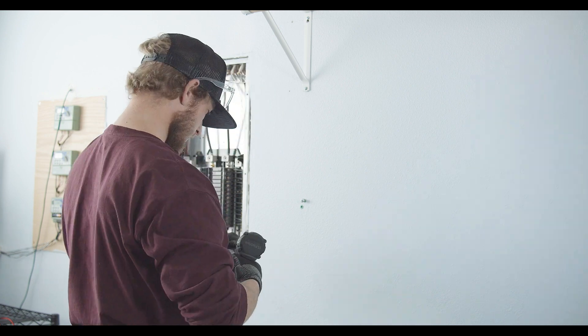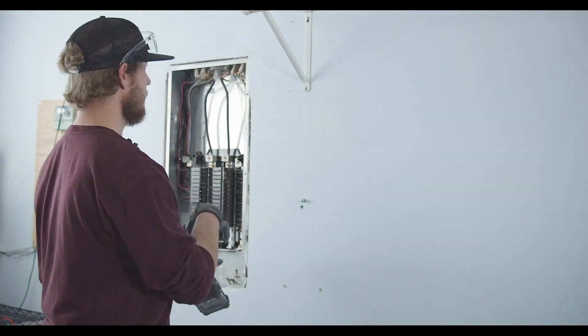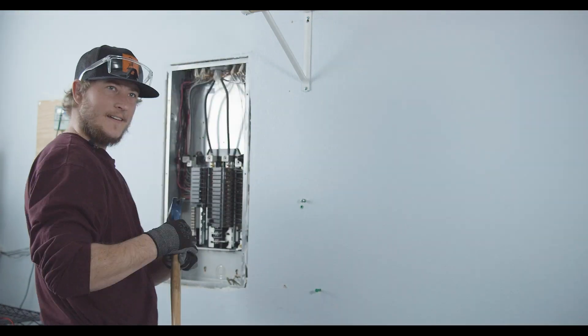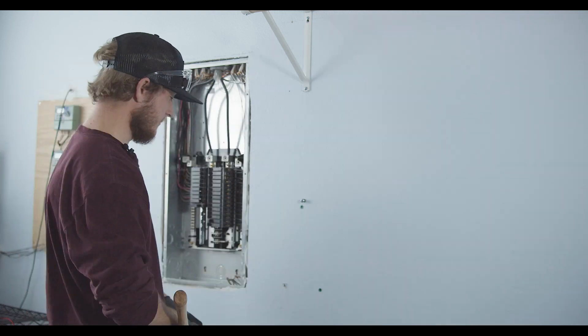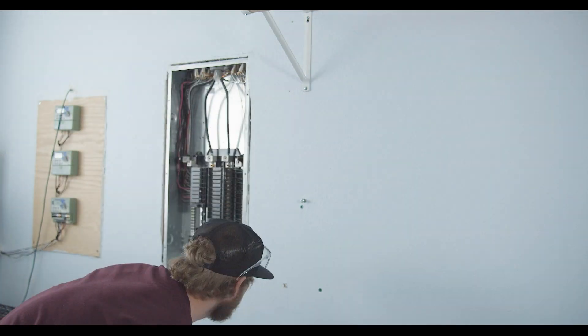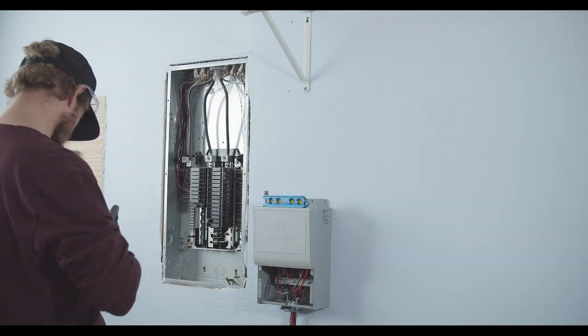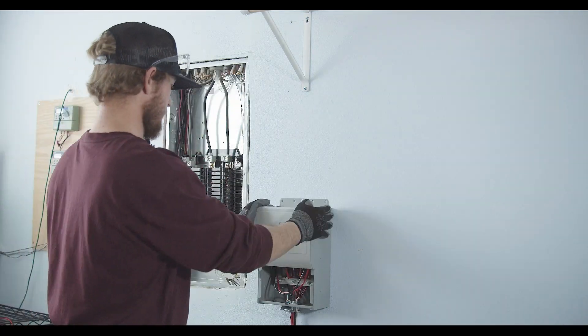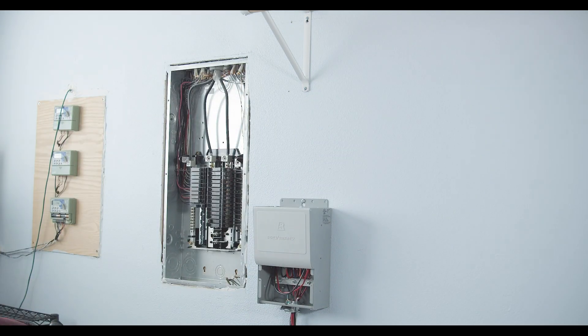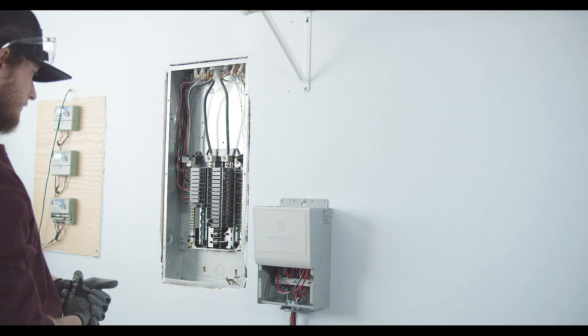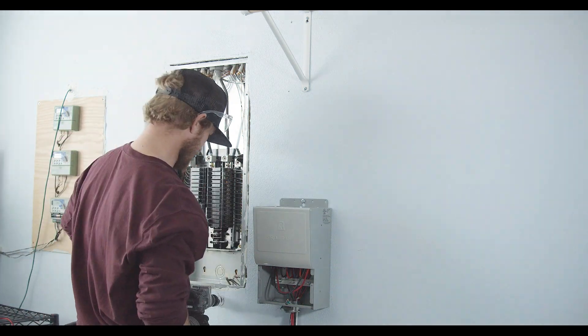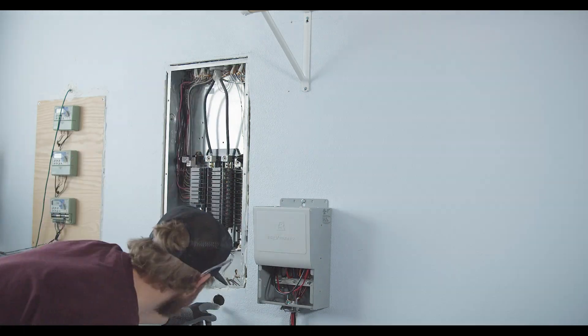I'm going to identify a location for this transfer switch and install it close to the sub panel. You need to keep in mind that the conduit and the wires that come with the transfer switch are a set length. I'm just going to install a few inches to the right of the panel and then I'm going to run the conduit and then cut into the wall underneath the panel.